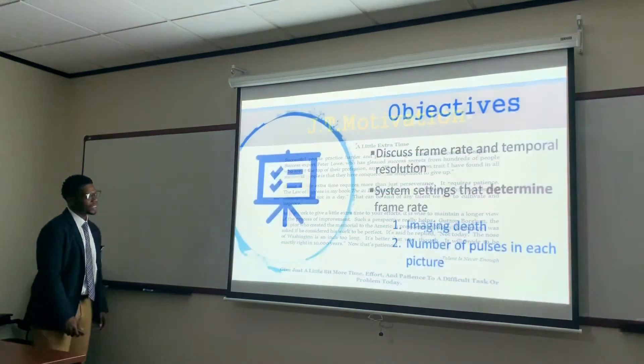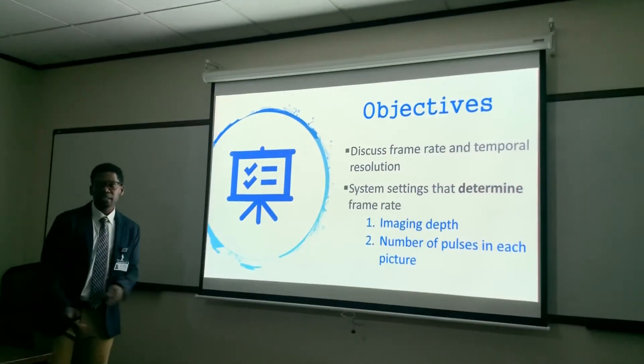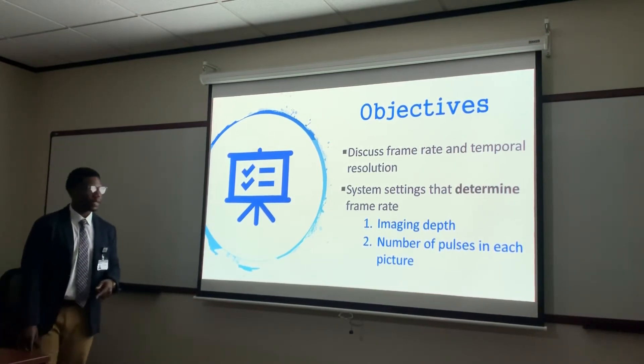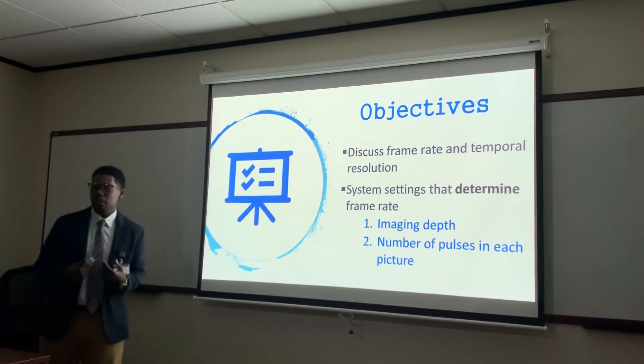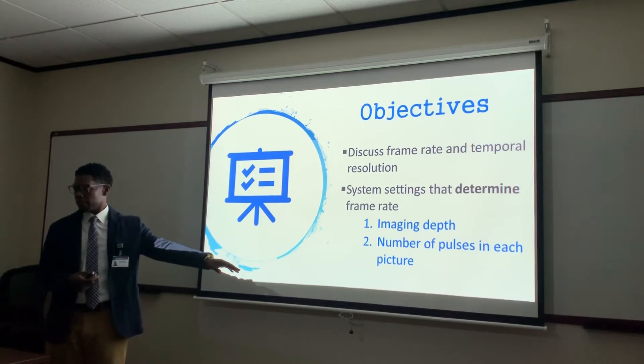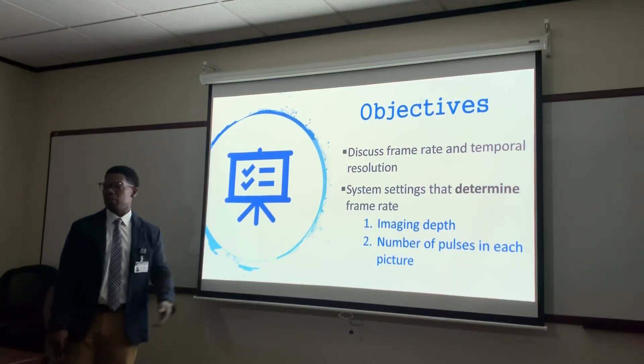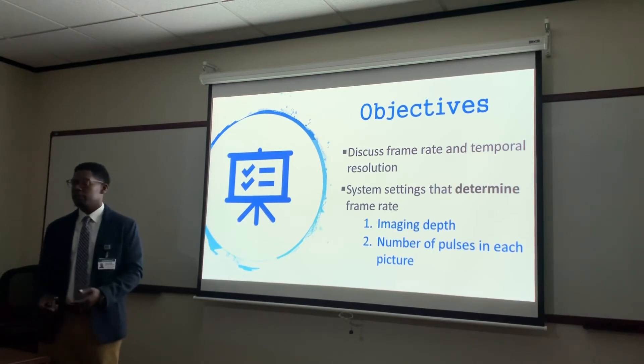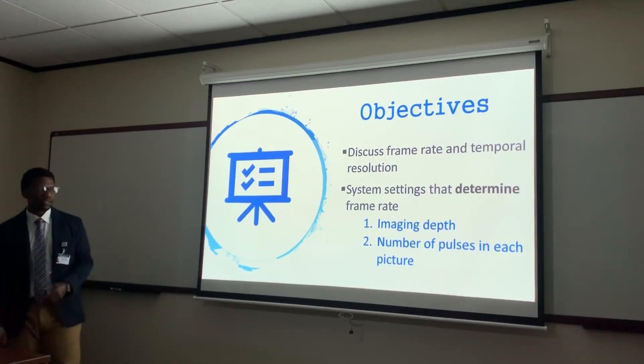Objectives of real-time imaging: temporal resolution — we're going to discuss frame rate and temporal resolution, and the system settings that determine frame rate. Those system settings include imaging depth and the number of pulses in each picture. Those are sonographer-controlled settings. As technologists, we can actually control the imaging depth — when we turn the depth button, we're changing the imaging depth, and we're also changing the pulse-repetition frequency.